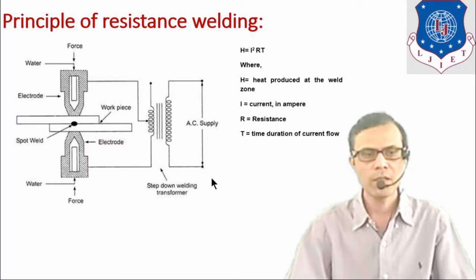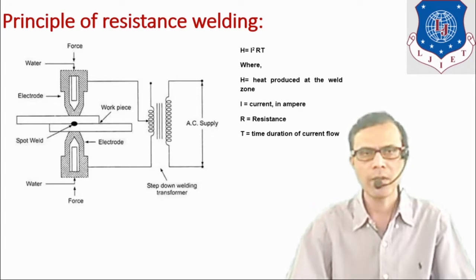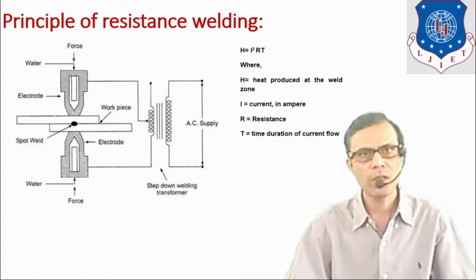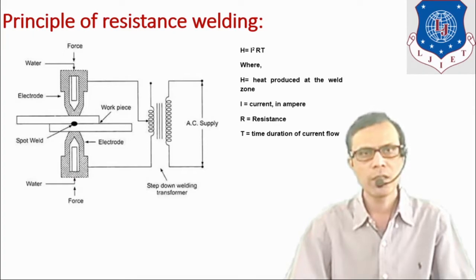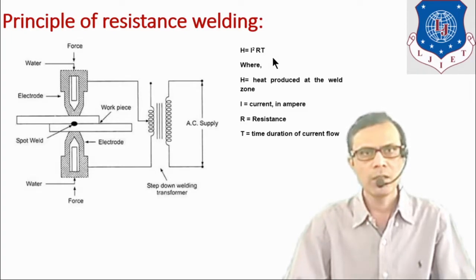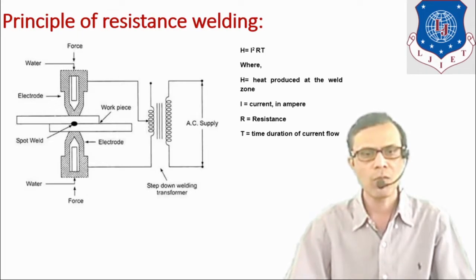Let us see in detail what is the principle of electrical resistance welding. AC supply is used because it can be transformed into high or lower voltage as per the requirement using a transformer. The basic principle is based on the equation H = I²RT.